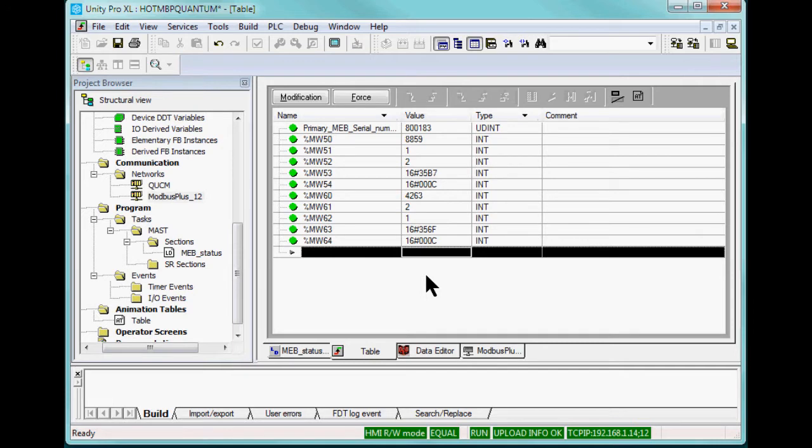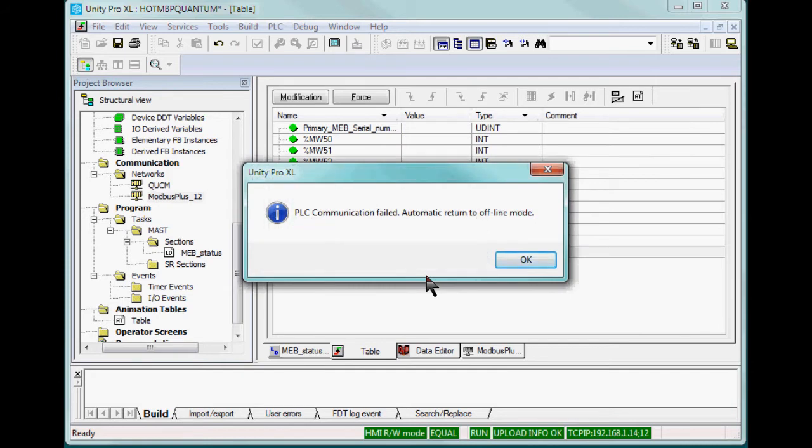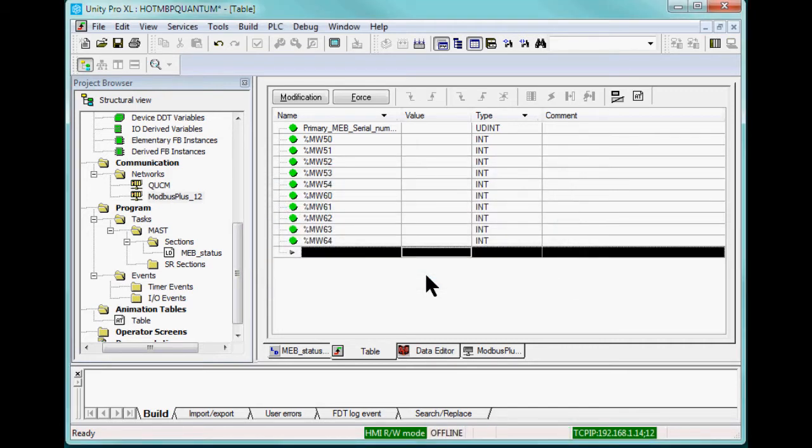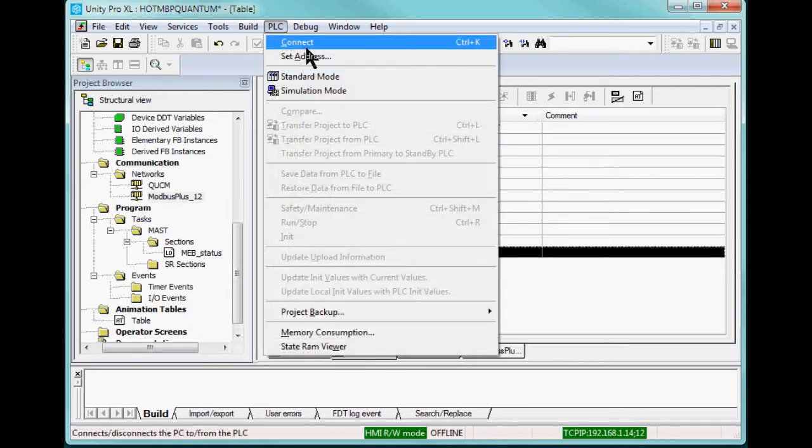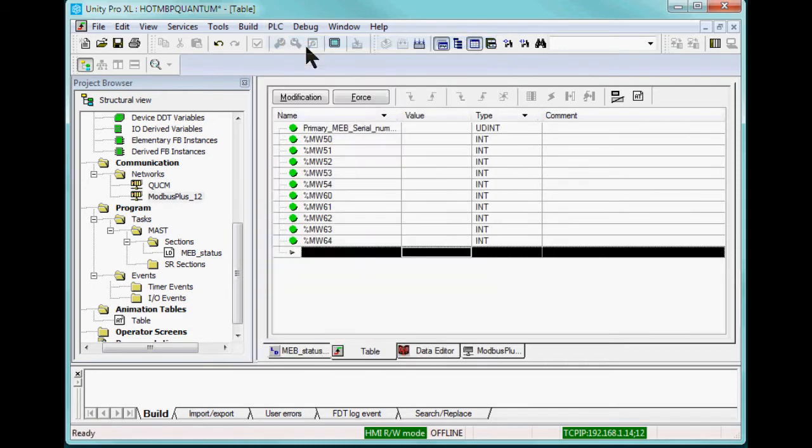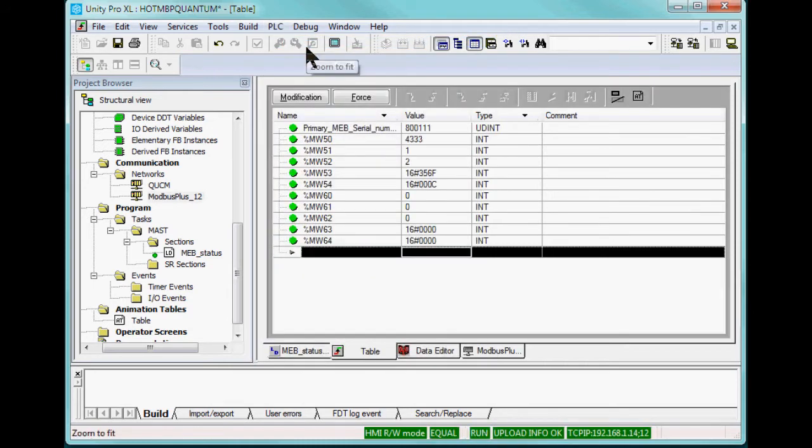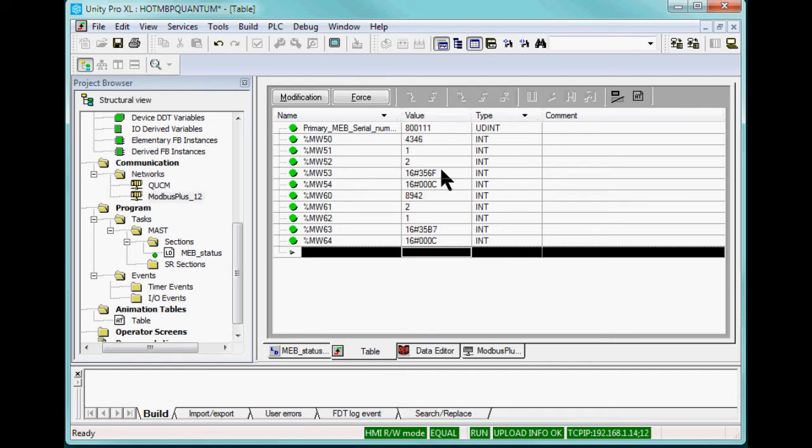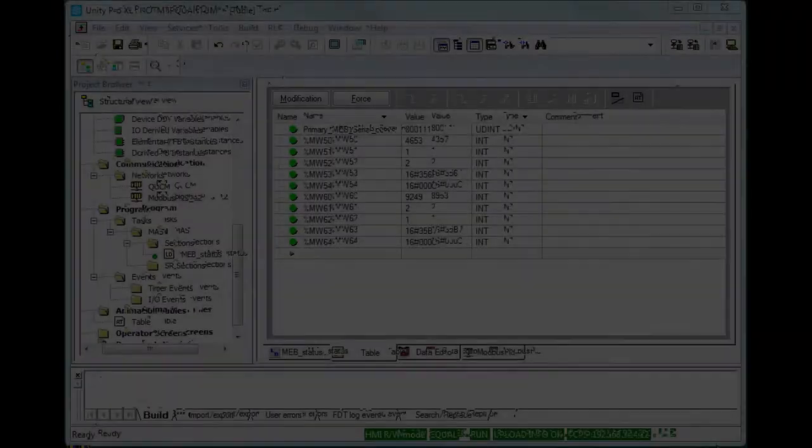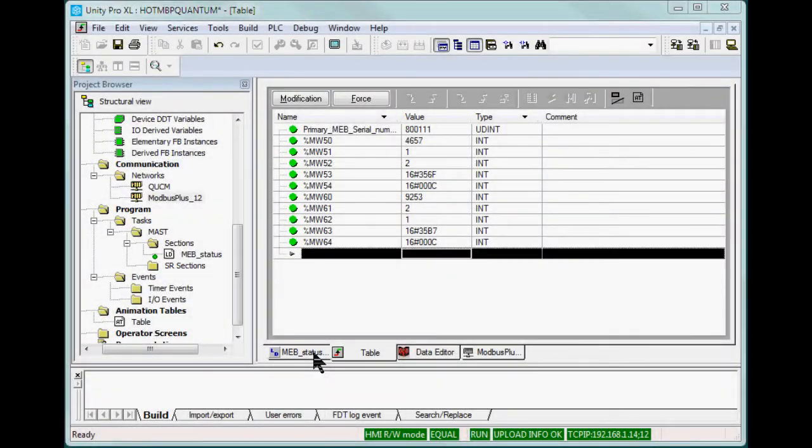Unplugging the primary unit causes Unity Pro to go offline. On reconnection, notice that the serial number of the primary unit has swapped with the secondary. Having the state of the primary and secondary MEB in the PLC makes it very easy to signal alarms on error conditions.